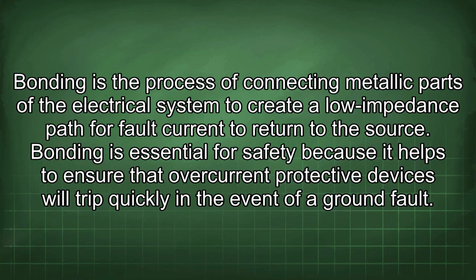Bonding is the process of connecting metallic parts of the electrical system to create a low impedance path for fault current to return to the source. Bonding is essential for safety because it helps to ensure that overcurrent protective devices will trip quickly in the event of a ground fault.